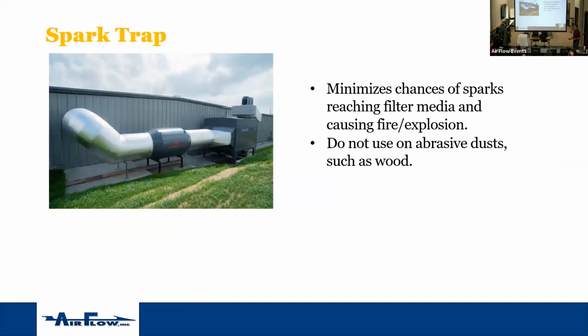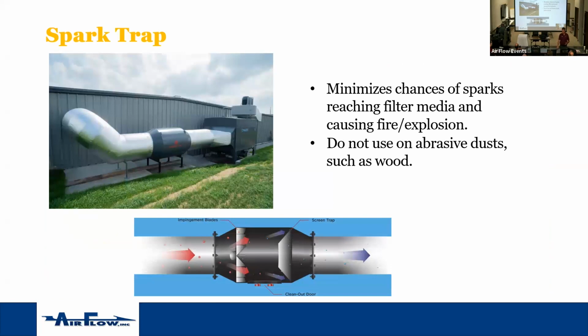Another way to mitigate on the suppression side, to stop a fire and explosion from happening, is to put in a spark trap. A spark trap will minimize any sparks going into it, and what it does is it takes the spark itself, runs it through a series of baffles and plates, and it actually fractures the spark, breaks the size of the spark down to a smaller piece, and then extinguishes it as it goes through. It's basically like if you're sitting around a campfire and an ember pops out and everyone takes the poker and you knock the ember down, and you keep hitting it enough times and it extinguishes itself and puts it out. That's basically what a spark trap does. You're knocking it down to smaller pieces. And we have one outside on the trailer we can go look at on your way out.